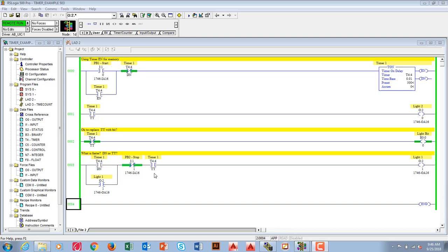Well, if you think about the order of it, the timer is timing, and then right at 5 seconds it stops timing and then becomes done. Because it stopped timing, this went from true to false, and then immediately thereafter this became true. So the done bit and the timer timing were not true at the same time.